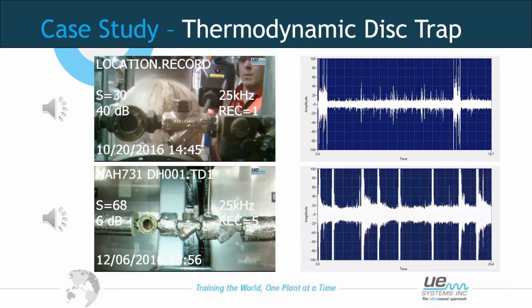So from this sound recording, we can see very clearly lots more turbulent flows. So we can see the trap opening and closing more and more each time. So this is telling me that the trap is working, but it's now losing its efficiency. Okay, so we can see that now this trap is removing condensate, but maybe not as efficiently as it should be. So this is an indication of a steam trap that is not working as well as it should be and could be on its way out. So we would maybe monitor this a bit more closely and take more readings.